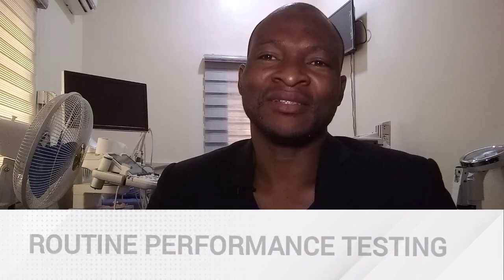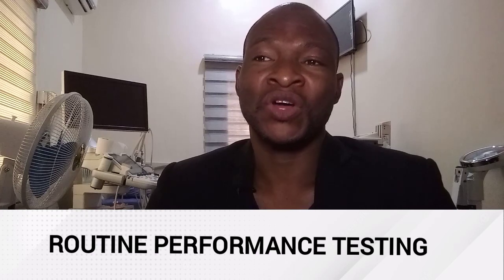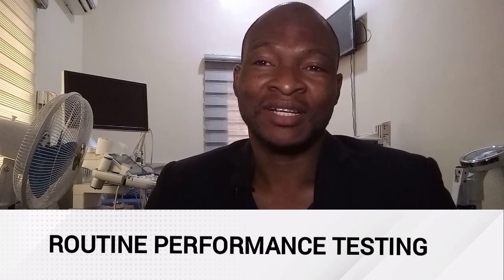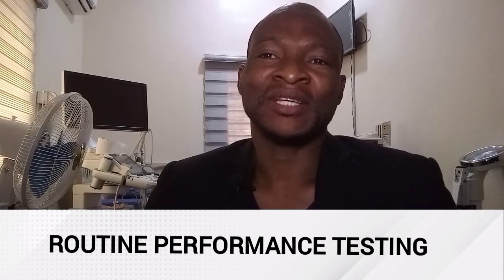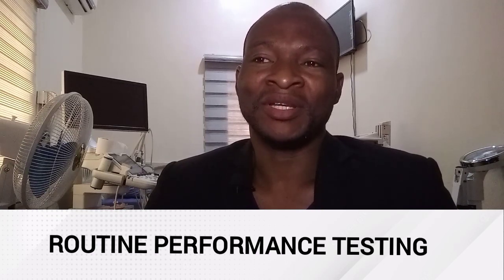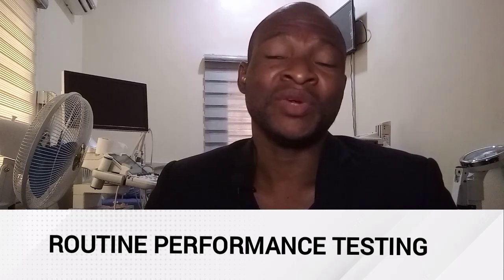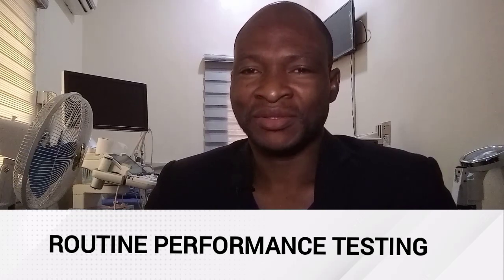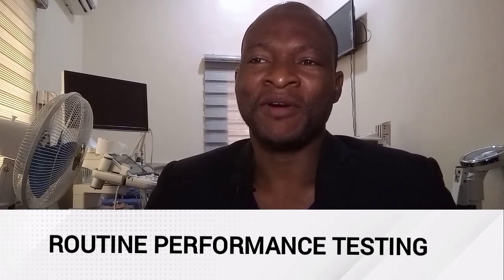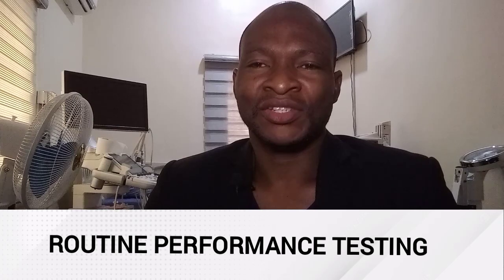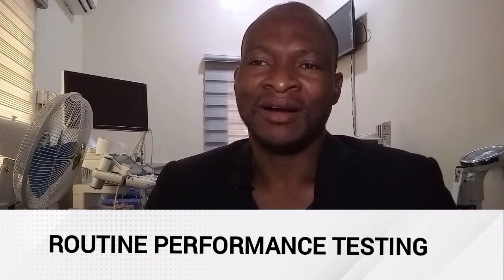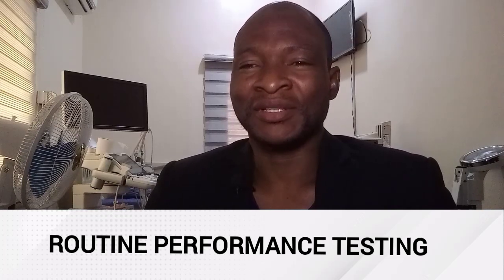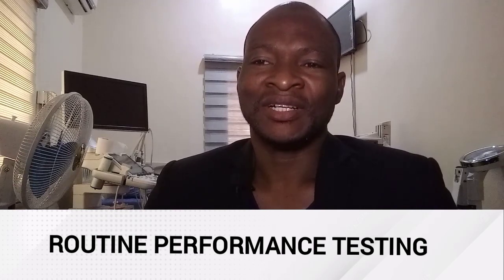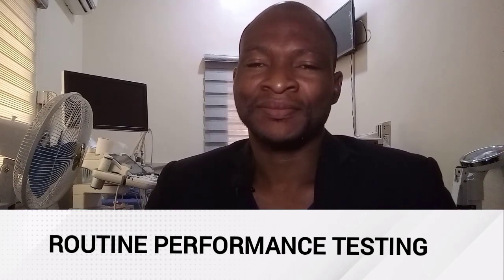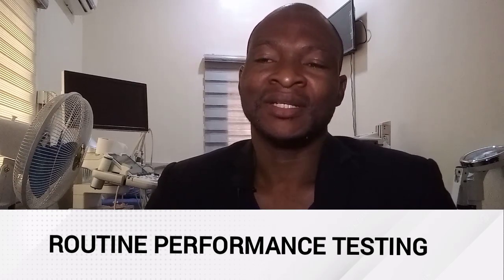Routine performance testing may be performed by a sonologist or a sonographer, or even the service engineer. Basically, the routine testing is done at a fixed time interval, maybe every 3 weeks or every 6 months or thereabout, to assess that the equipment is performing consistently. This is done using test objects like phantoms and standardized system parameters. The relative change in test values over time is monitored and requires regular and accurate record keeping.